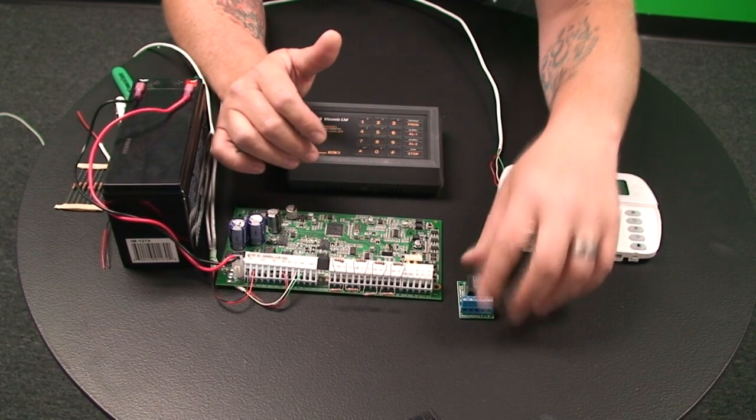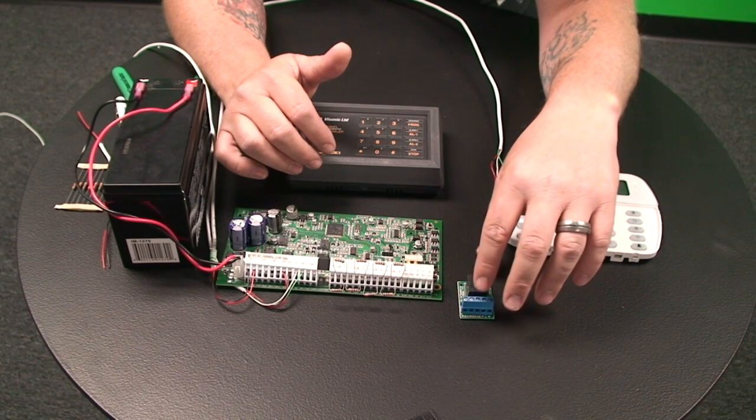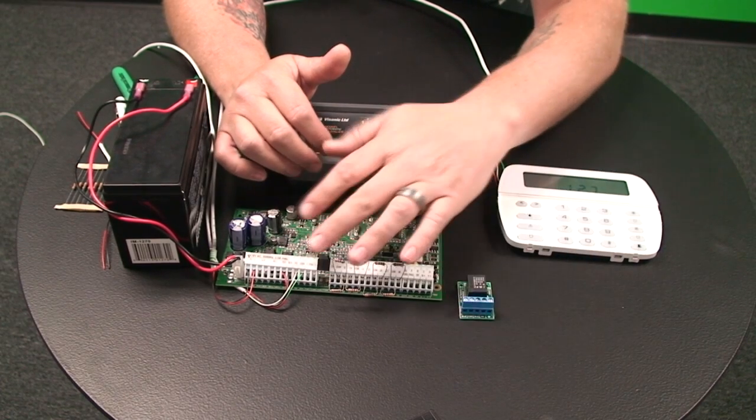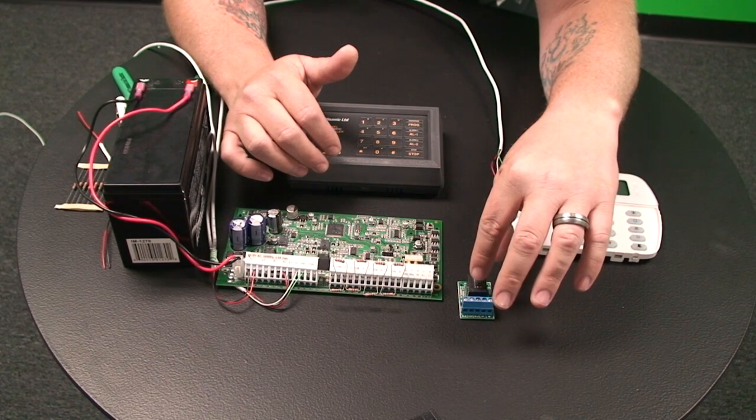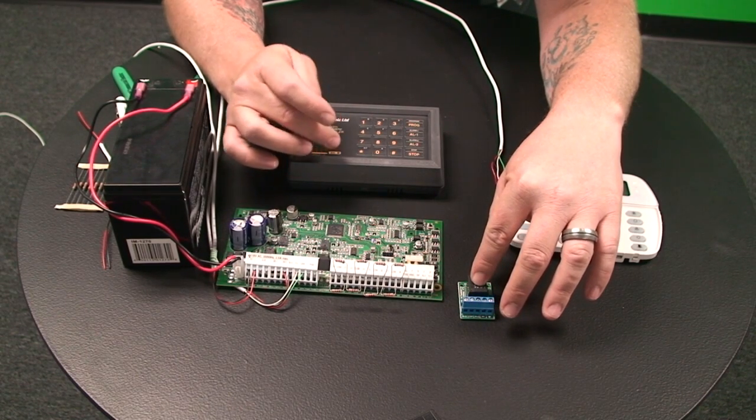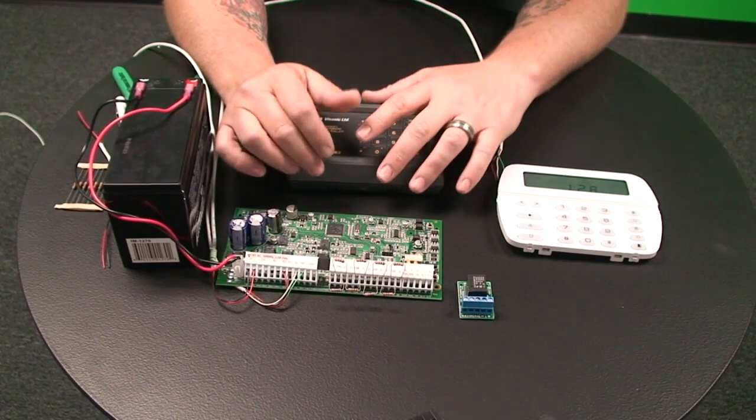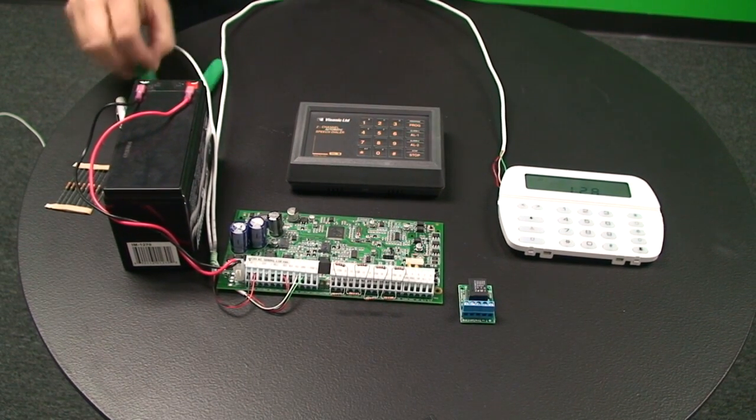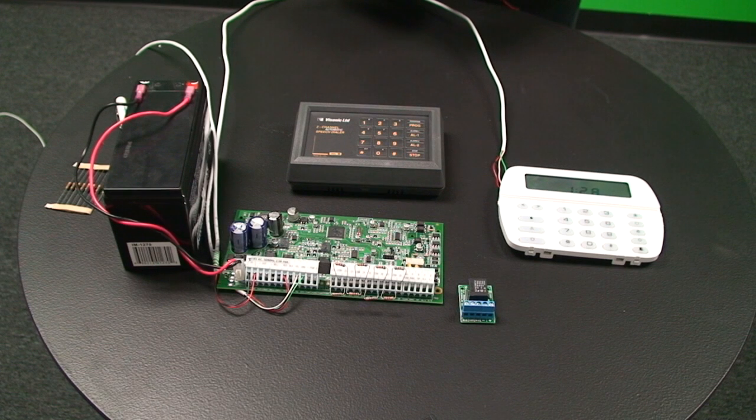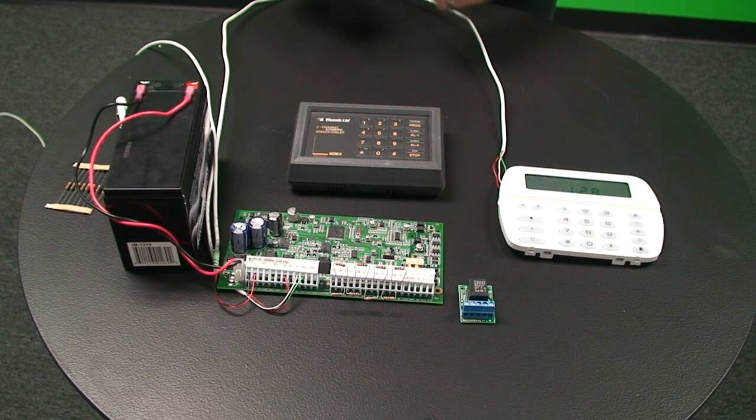So what this relay does is it'll be provided power from the control panel. When it does get its power it will give you a dry contact closure which will in turn trigger this dialer. We're going to start by hooking up this relay to the control panel, and this will be triggered by the bell circuit on the panel.